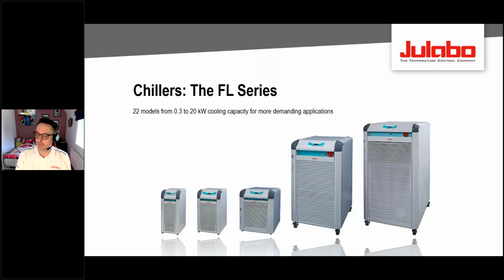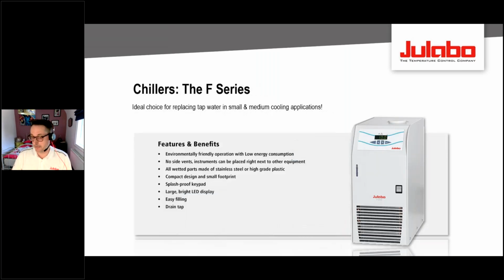The second thing you need to think about is flow rate through your system. To remove heat from a condenser, you need to flow water through it. The F series, which is quite basic, has very simple pumps that will pump quite happily through one or two glass condensers.